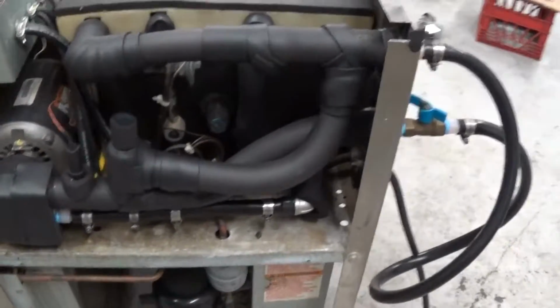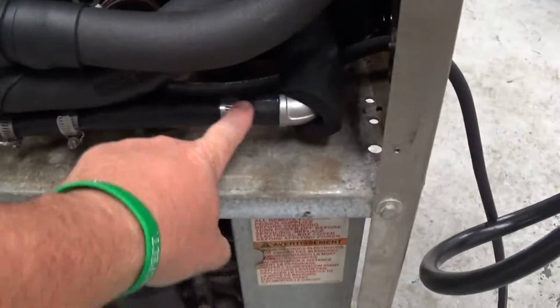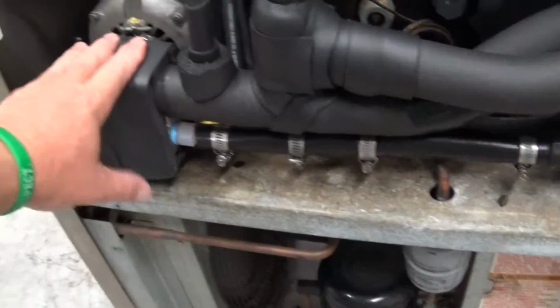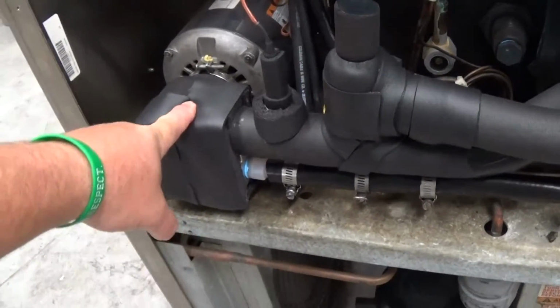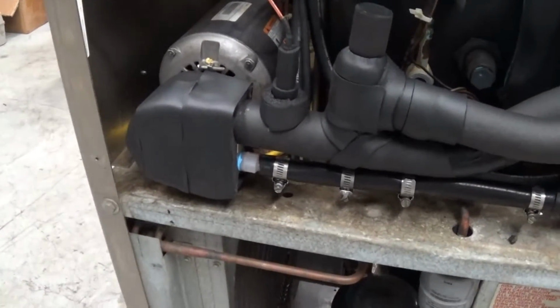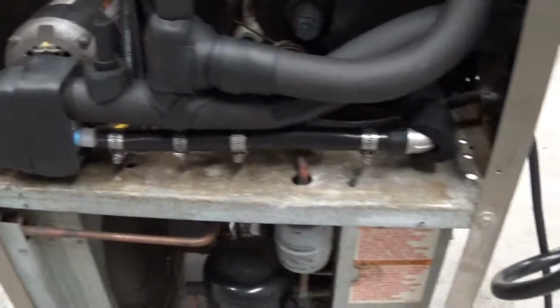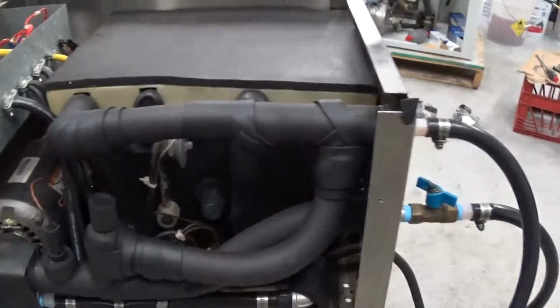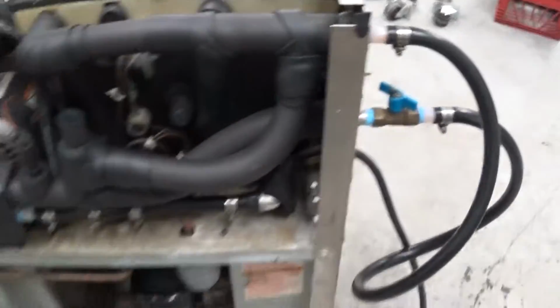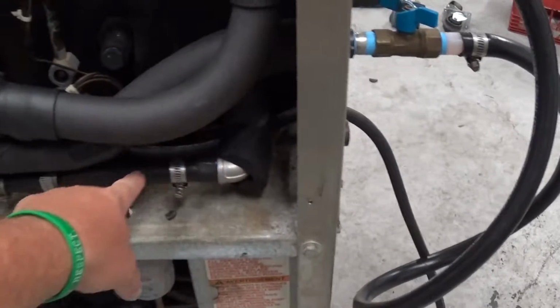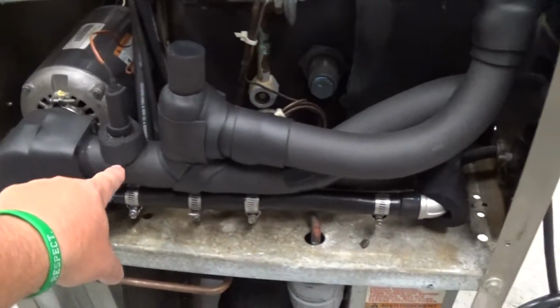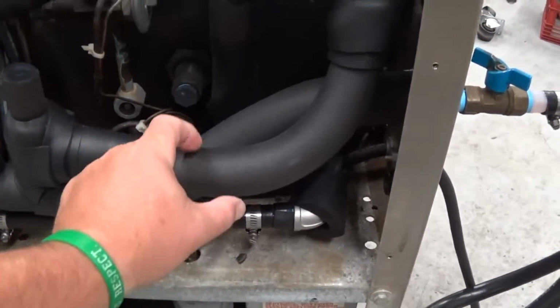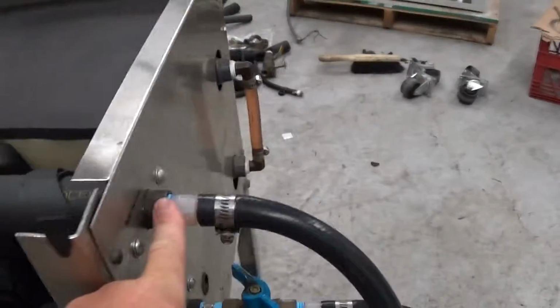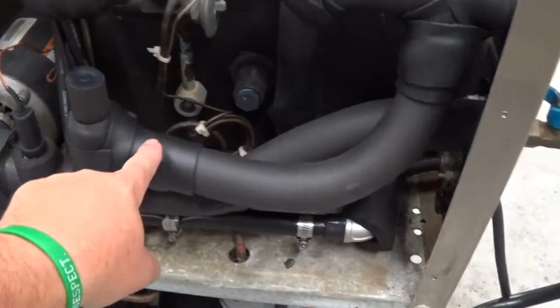One last thing we'll do before it ships out is we'll put one more piece of insulation on this suction line. This is your positive displacement pump. That's a brand new stainless pump, about 200 bucks, the pump head, which is kind of nice. This is all new piping here, and we like to insulate everything, which we have done. Now, we're drawing off our tank into our pump. Now this line, follow my finger, goes out to process. See, it says there, to your process, and this one returns back. This here is your bypass line.